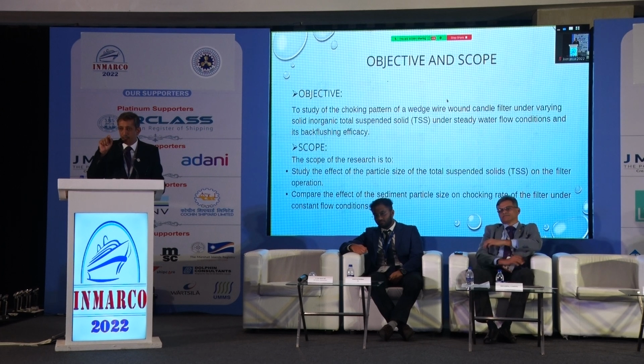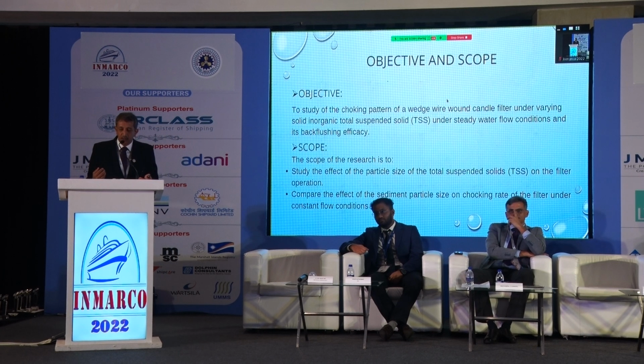So the water flows between two triangular sections with the flat face facing the outside world. That is the raw water. There are two types of filters: either the water flows from outside the candle to inside the candle, or from inside the candle to outside. For basket filters, generally it flows from inside to outside with the suction nozzle in the inner ring. But there are enough designs where the water direction is reversed. It's all individual patented filters. But at the end of the day, all of these struggle to cope with the high TSS load.